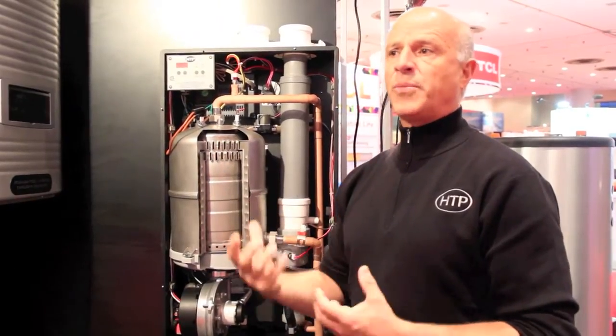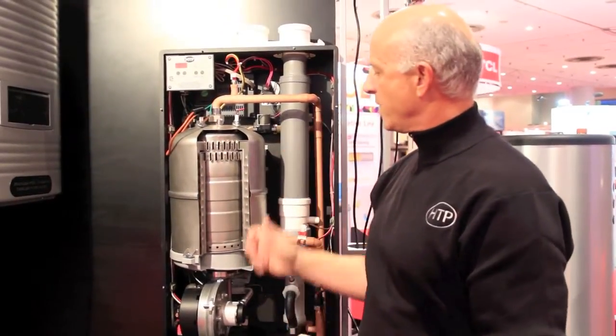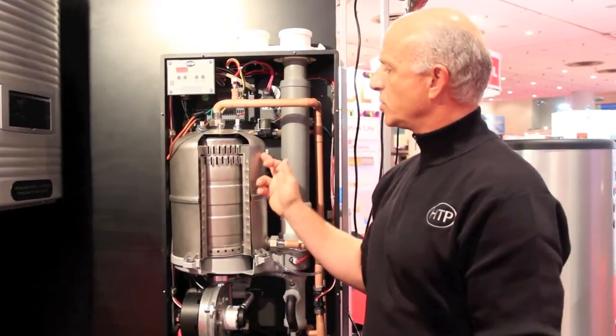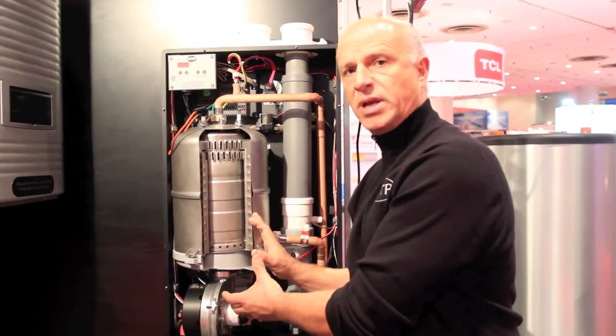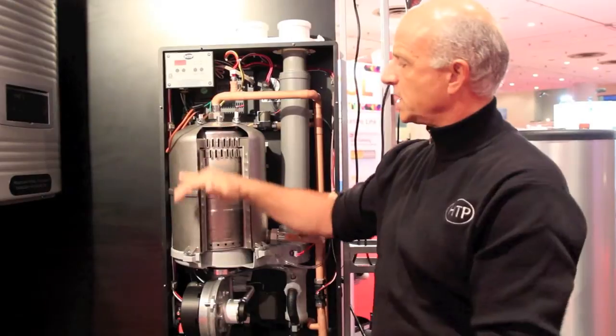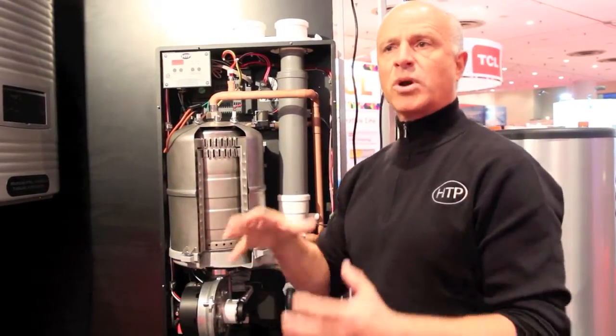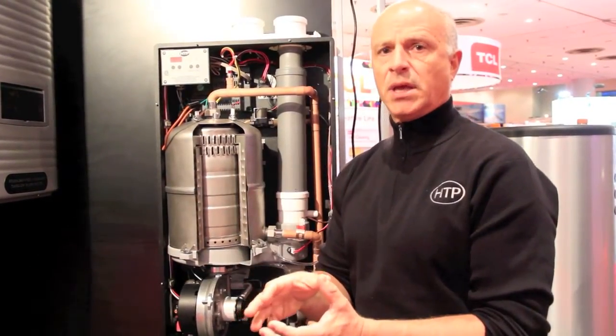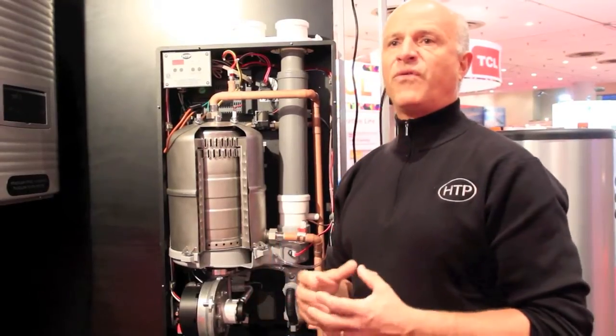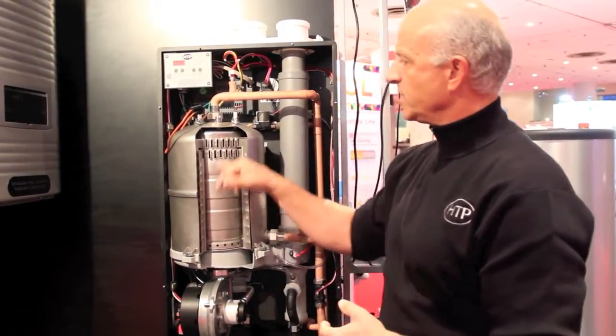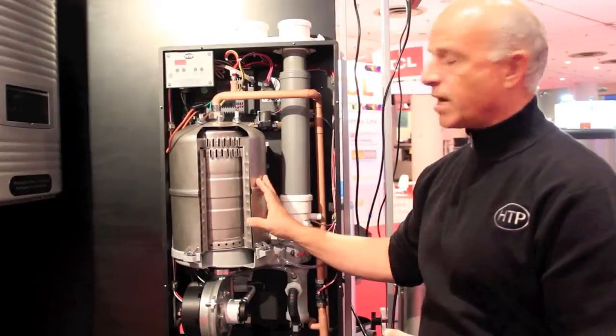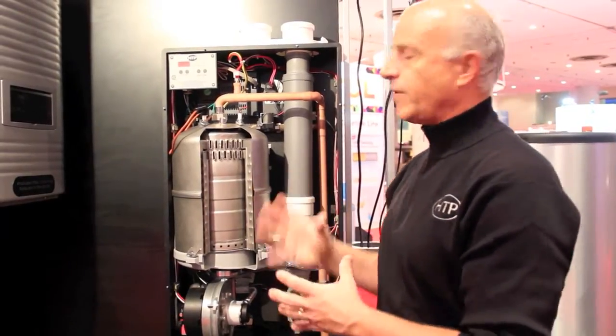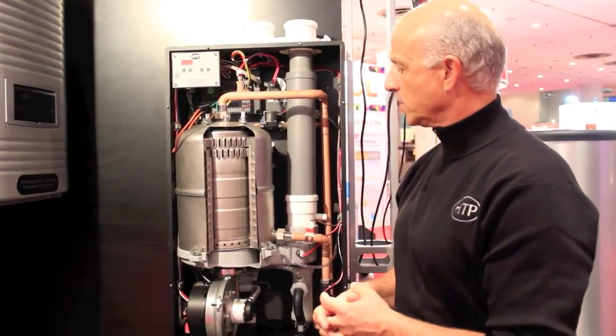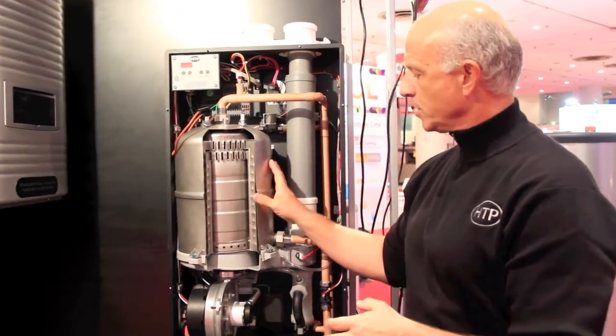So we've come up with a very unique process through that valve. We're going to circulate the water through this, and we're going to bring that temperature down inside the module, so the temperature from the top to the bottom is the same, and we're going to lower that temperature significantly, which will help avoid long-term corrosion of this heat exchanger. The whole unit's made out of 316L stainless steel, very high-grade stainless steel, very well built. It has a 10-to-1 turn down.